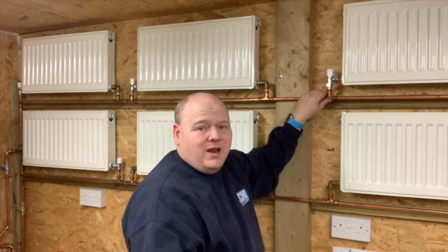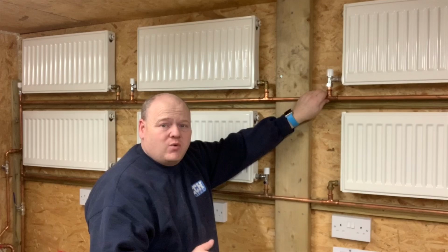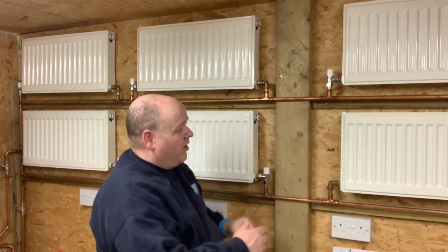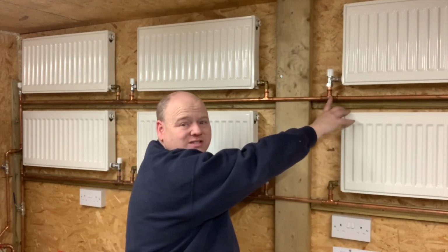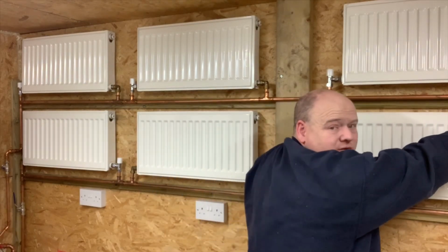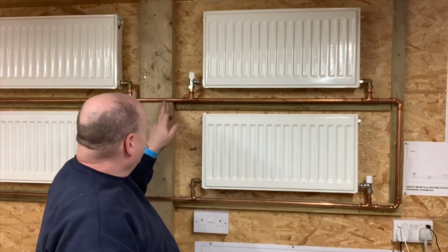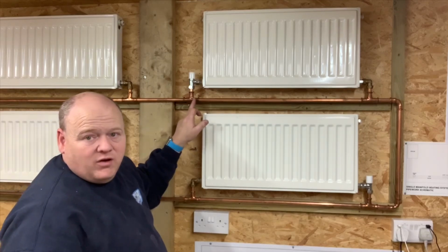But normal domestic, it'll just be underfloor, so it might be a little bit hard to see that it's a one pipe system. Sometimes you might have to lift the floorboard up just to have a quick look, and what you'd be looking for is if it's got a T, and if that T connects into the other radiator on the other side. I'll just zoom in and show you that there. So if it connects in on the other side, we know the flow and the return are both connected together.